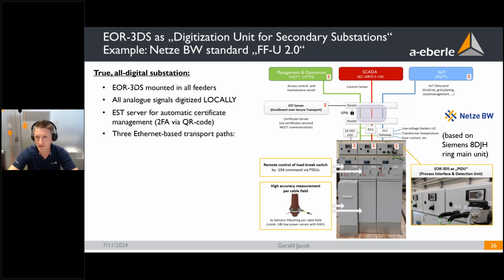And it's the same in the cable fields. Here we also have the load breaking switch and the earthing switch, and 2 further items of information that are wired to the binary inputs 5 and 6. So all analog signals, binary signals, as well as the measurement, are digitized locally in each field. And this you can also see here in the transformer field. You see here a Harting connector. This is only supply voltage, and the only further connection are 2 Ethernet cables, so a redundant Ethernet connection. There is no other connection to the complete secondary compact switchgear station here on the secondary side.